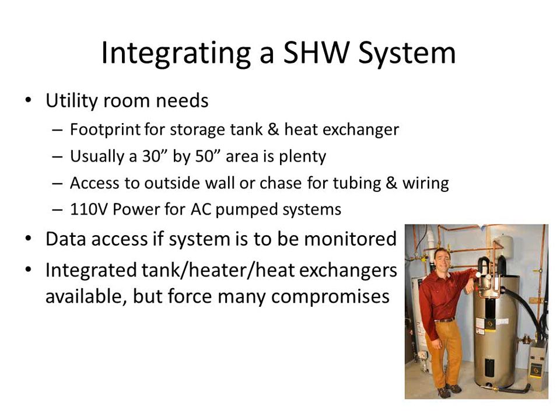When you have a single tank instead of two, you're going to see some mixing. And what that's going to do is it's going to end up both warming up your solar storage reservoir and cooling down your resistive reservoir, which is then going to cause your resistive element to fire more often and use more heat. And it's going to make your solar system work less efficiently in the wintertime. As that gets warmer, the temperature gradient drops, and therefore your heat exchanger is less efficient. So your heat exchanger is going to pull heat out of the glycol and into the water more and more effectively the colder your water is. So having these combined systems drops system efficiency both on the heat transfer side and on the lack of storage.